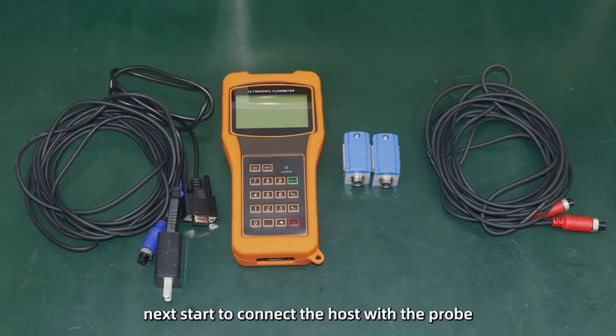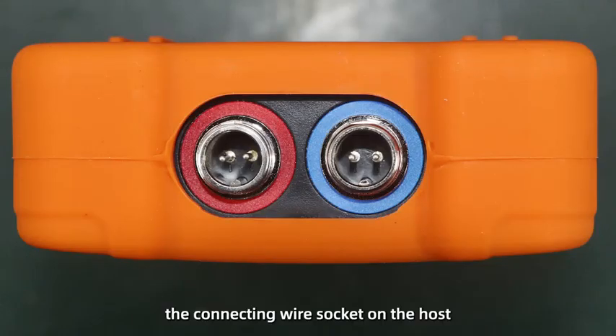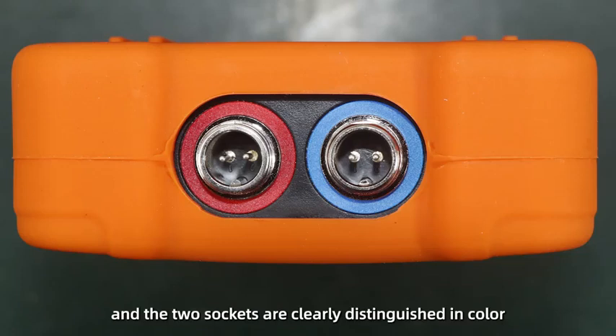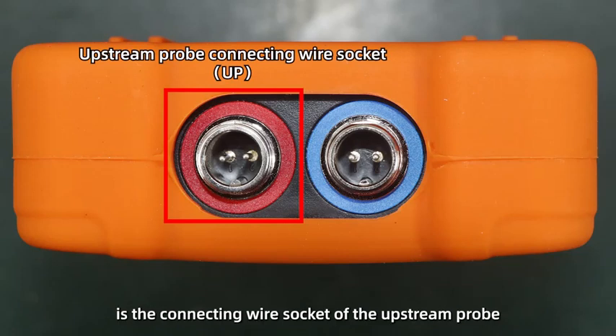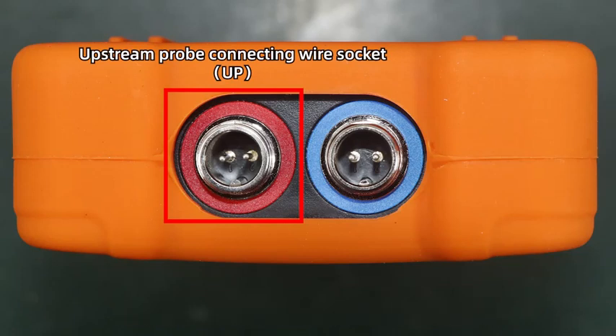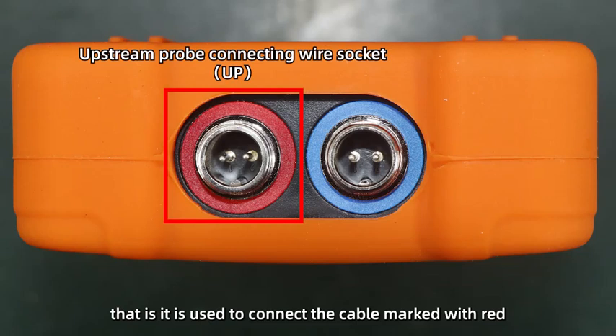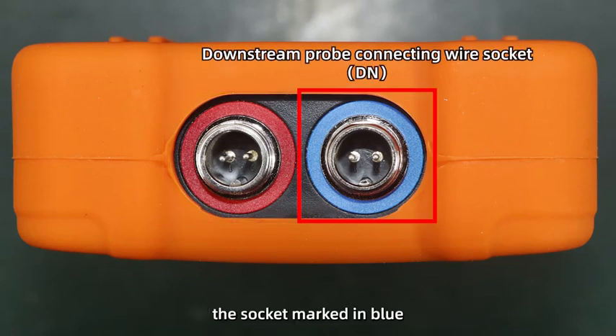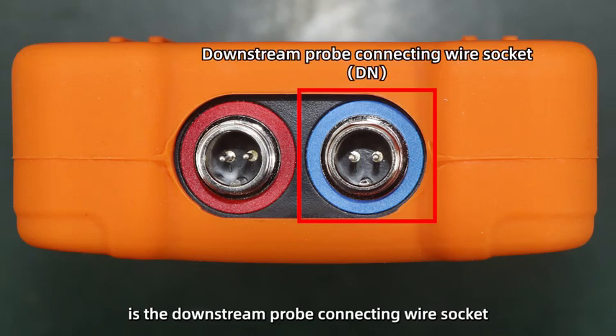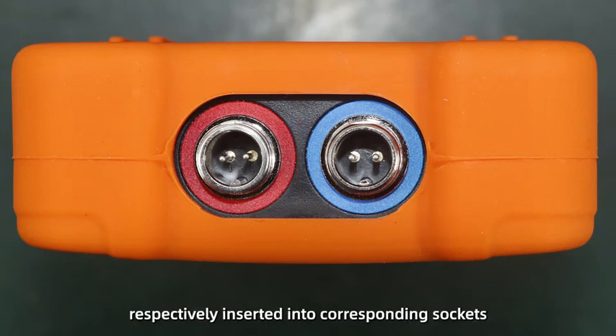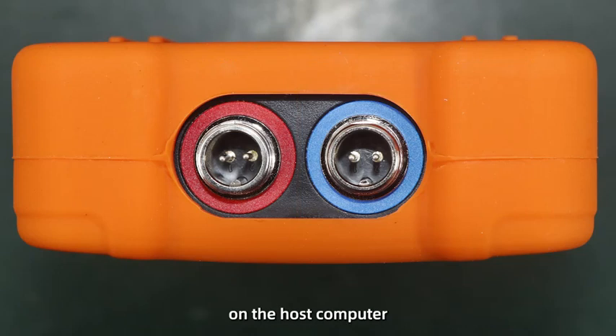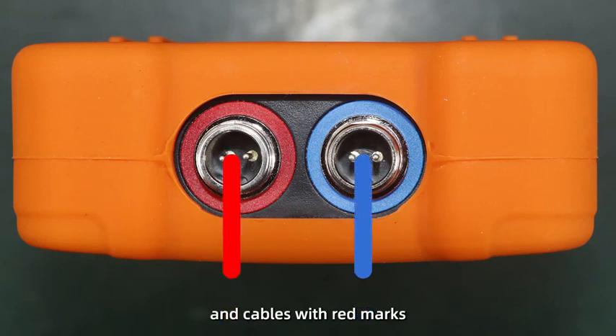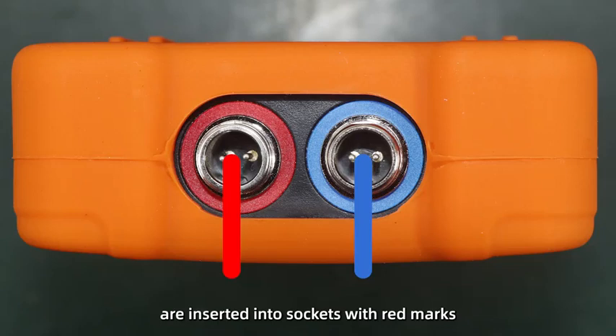Next, start to connect the host with the probe. The connecting wire socket on the host is at the top of the host, and the 2 sockets are clearly distinguished in color. The socket marked with red is the connecting wire socket of the upstream probe, that is, it is used to connect the cable marked with red. The socket marked in blue is the downstream probe connecting wire socket, which is used to connect the cable marked in blue. Firstly, 2 cables are respectively inserted into corresponding sockets on the host computer, and cables with red marks are inserted into sockets with red marks. The cable marked with blue is inserted into the socket marked with blue.